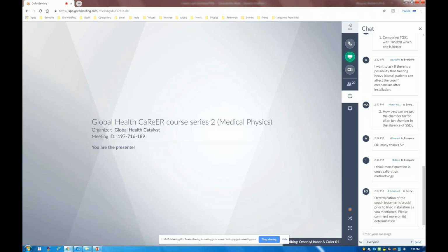So there are tests once the Linac is in place, but before the Linac is in place, as physicists, we actually don't determine the couch ISO center. You can work with the manufacturer and make sure that it looks fine, but the ISO center is defined with respect to the Linac as well. So without the Linac, it doesn't even mean much to have the couch ISO center. It's a rotational axis that you would say is fine or not. Okay, thank you.